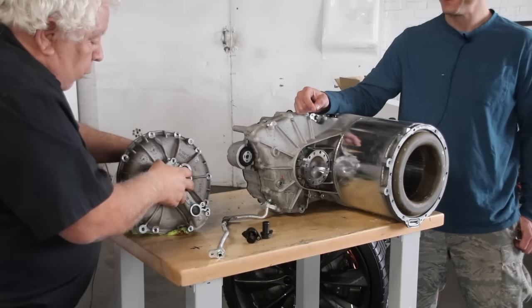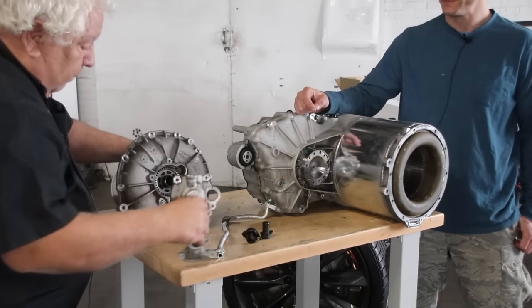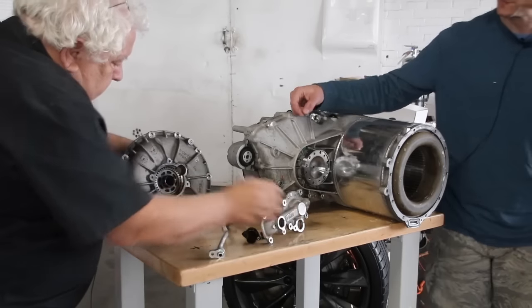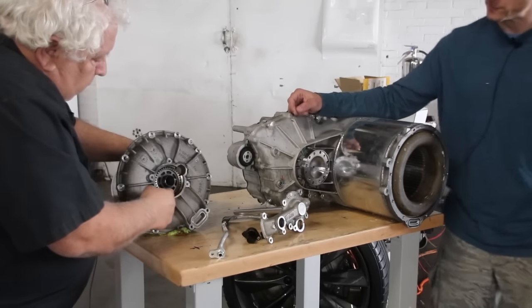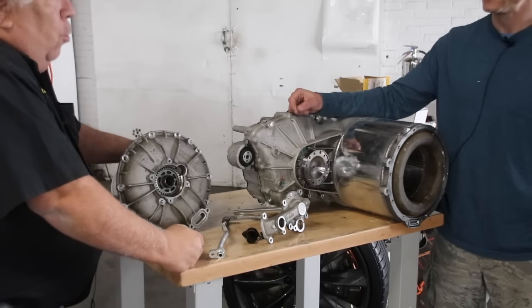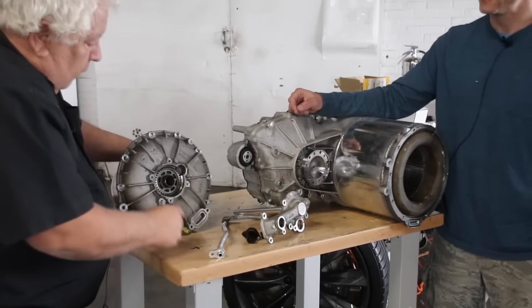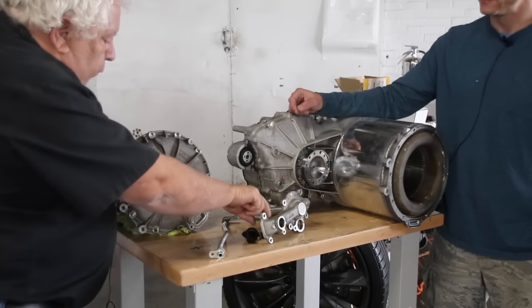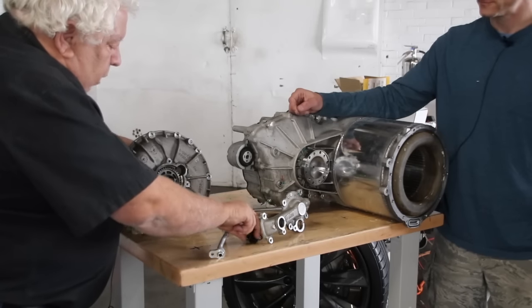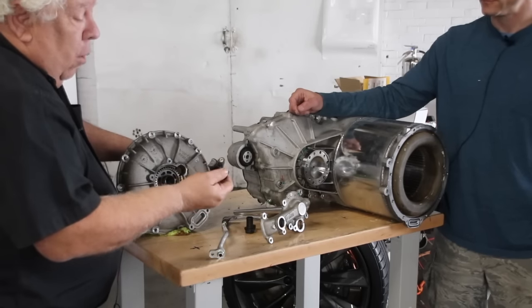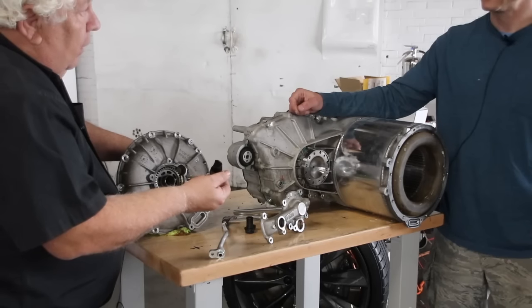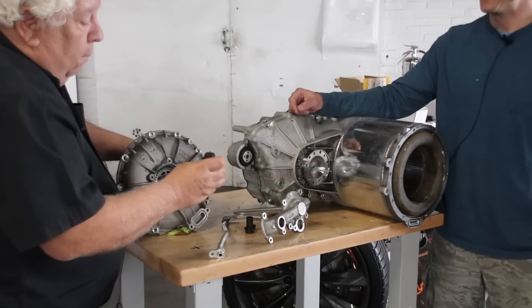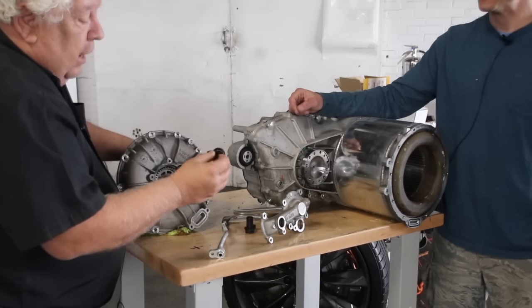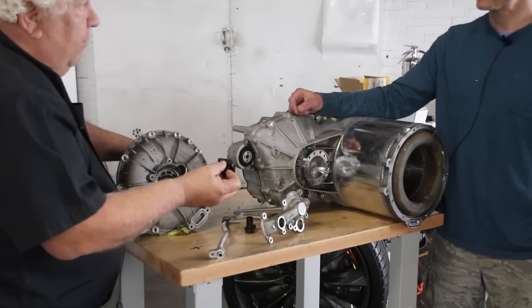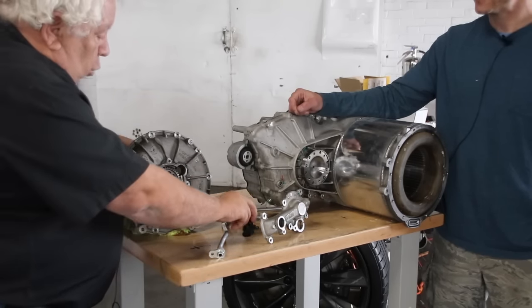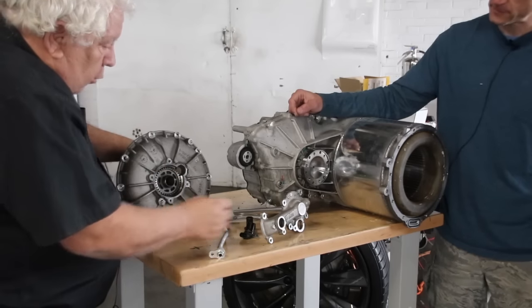I was enthralled with this particular scheme, because here is a very solid tooth gear. Encoders go bad a lot. This is a very solid tooth gear on the end of the rotor shaft, and a very solid, but also probably commonly available pickup. This is just an inductive pickup, like the one we used on the Escalade to pick up the ring. So that's our encoder.